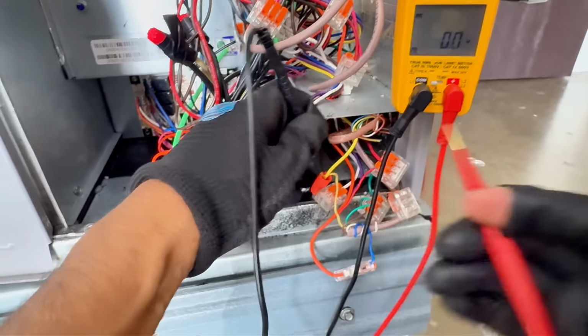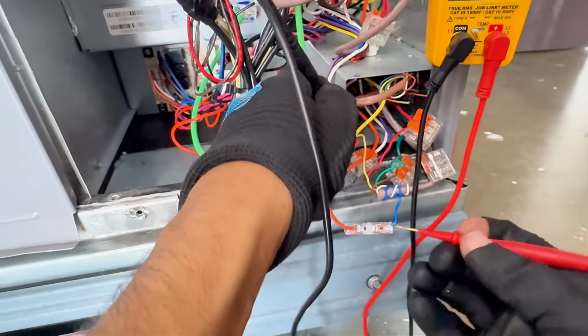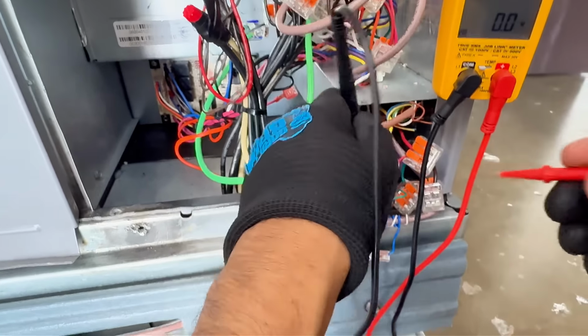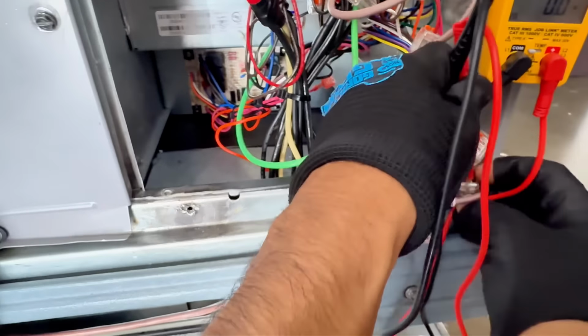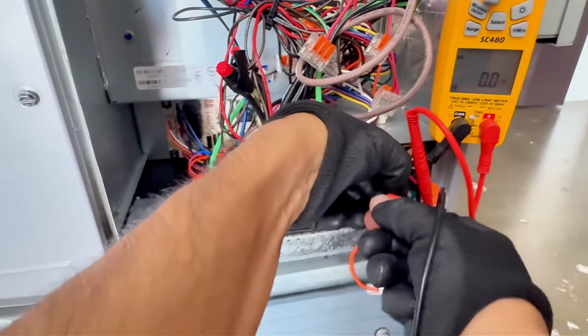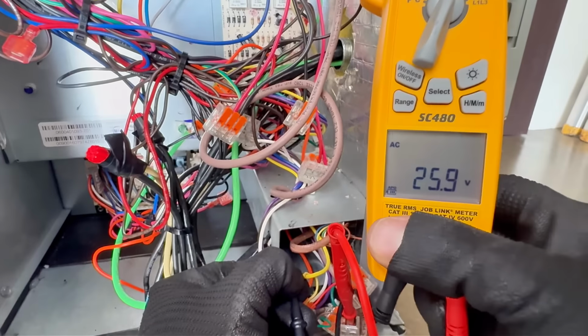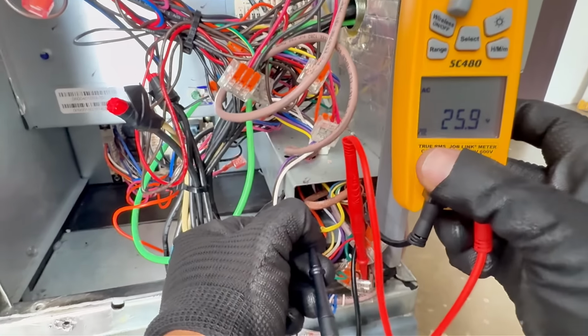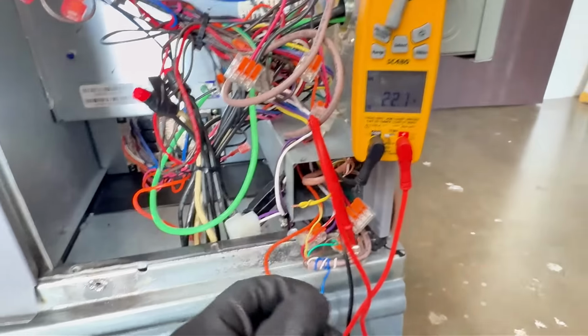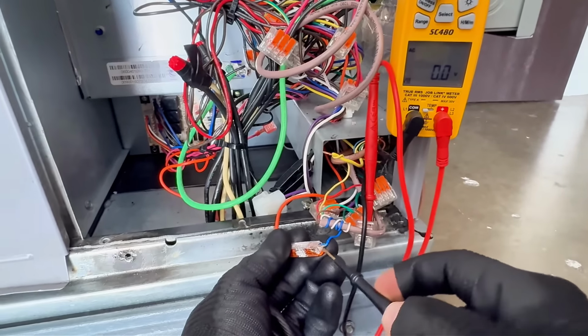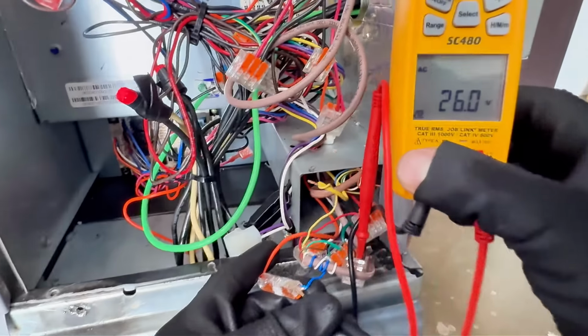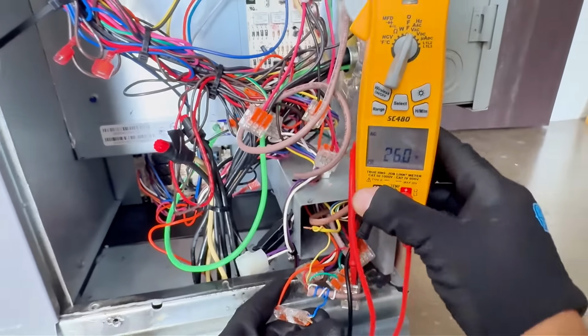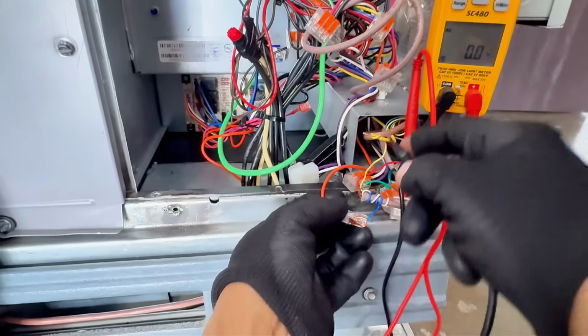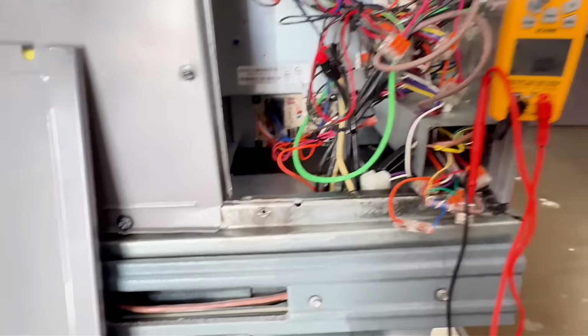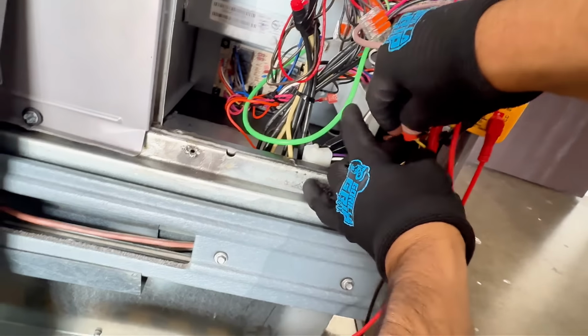So I'm going to go ahead and put it right there on yellow. And on my common, what are they using for common? Brown. So I'm going to put in my yellow and common. Okay, just bear with me here. Let me open this up here. Okay, you see? So my thermostat is calling for cooling, and this is a heat pump. So between common and my reversing valve, I want to make sure I have 24 volts too, because it's a heat pump, and we do. So the thermostat is doing its job. I'm sending 24 volts to Y, my compressor, and for the reversing valve. So now I know that my issue is not my thermostat, because the thermostat is doing its job.